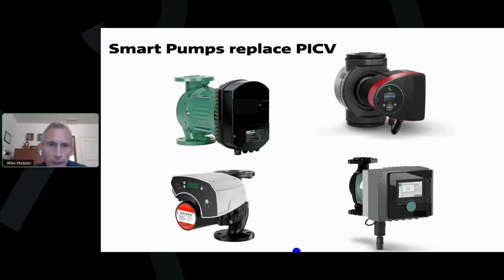Time to move on. So here, what I'm showing are ECM circulator pumps, a variety of manufacturers. Mine happens to be the one in the upper right-hand corner. When we get into distributed pumping, what we're doing is replacing the control valves on the air handler pumps that require a big pressure drop, and we're replacing those with smart pumps. We're going to get better flow control with these pumps, and there's some advantages to the pump. So I'll go through some of the advantages first, and then we'll get into the distributed pumping concept.